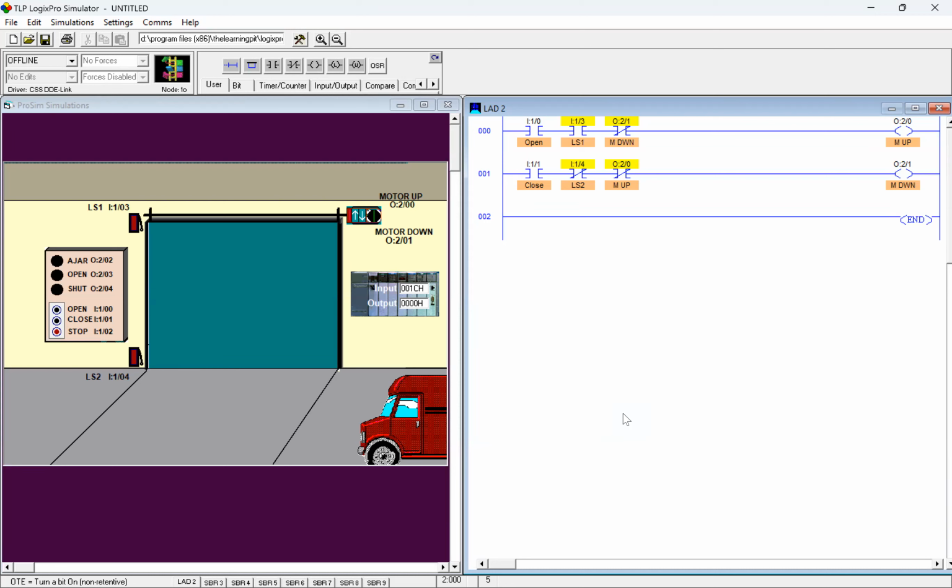That's done mechanically with a little thing in between them that blocks one when the other's going. You also have contacts you add on there that are normally open and normally closed, and you also do it electrically in the field where you're doing the forward reverse. You do not allow the forward reverse to happen electrically. So you're redundant: you've got a mechanical and an electrical wiring situation that you do that with.